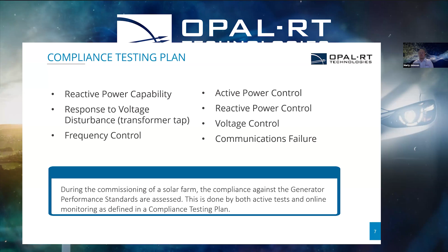So this is what we would typically test on site. We test our reactive power capability and how the control system responds to voltage disturbances. We test frequency control for frequency deviations, active power control, reactive power control, voltage control, and communications failure. When we do this commissioning of a solar farm, it's required. It's called the R2 stage in Australia. We do this commissioning and then test the compliance of the plant against what we've said it will do in the modeling phase.